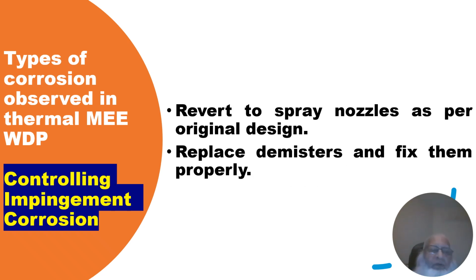This slide shows how to control impingement corrosion in MEE WDP. It was recommended to revert to spray nozzles as per original design and replace the demisters and fix them properly.